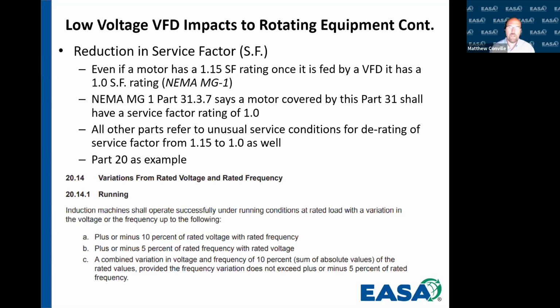So what does NEMA have to say? NEMA says that effectively, as soon as we put a motor on a variable frequency drive, its service factor rating is 1, even if it had a 1.1 or 1.15 service factor rating. This comes from NEMA MG1 Part 31, Part 3.7. And it says that a motor that is covered by the Part 31 standard, which is for use on an inverter, shall have a service factor rating of 1.